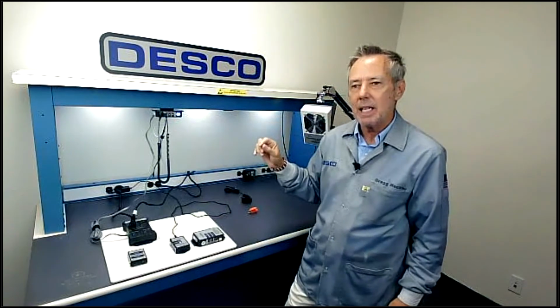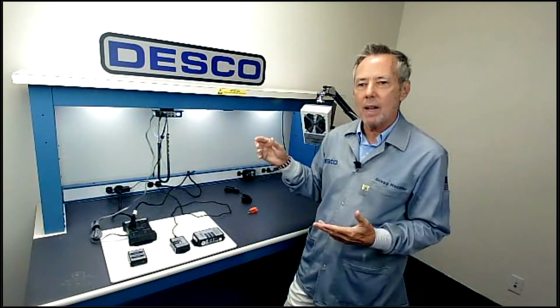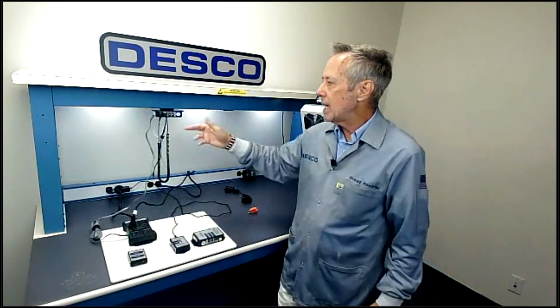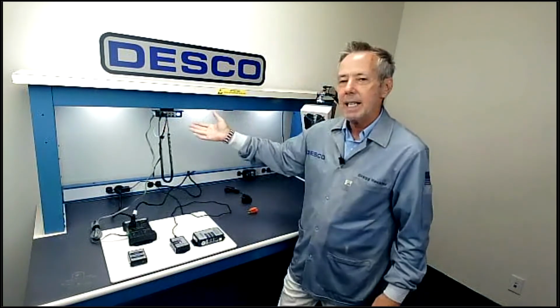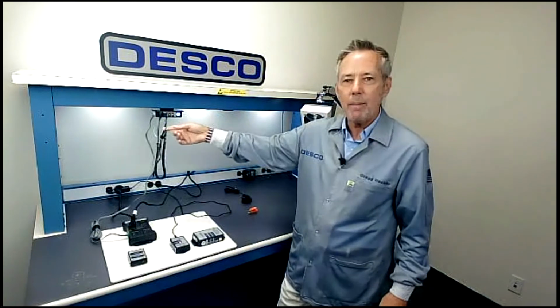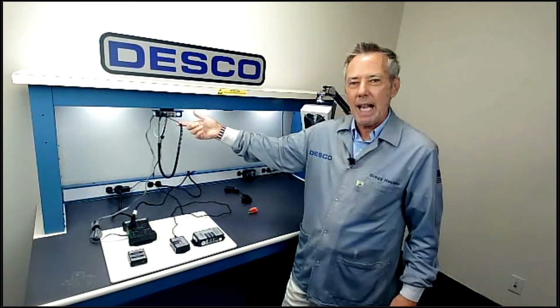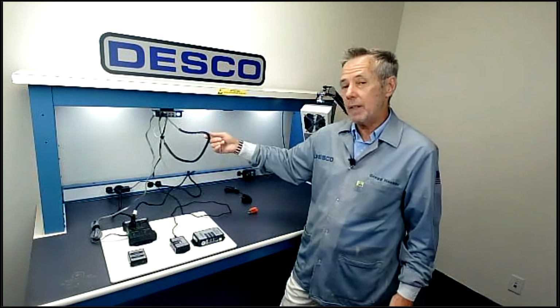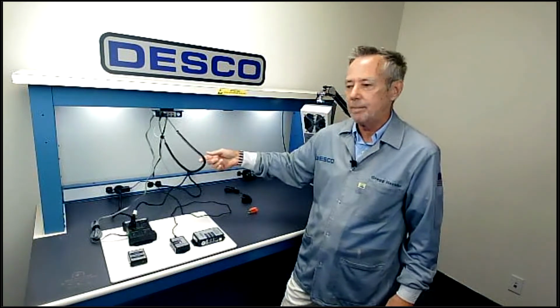banana plugs and jacks, but there are some wrist strap cords where the springs break easily or get sloppy and loose, and it wouldn't be uncommon to yank. In fact, I've been in many places where people are taping their banana plug into their jacks. So that's a great feature so people don't accidentally remove their banana plug.